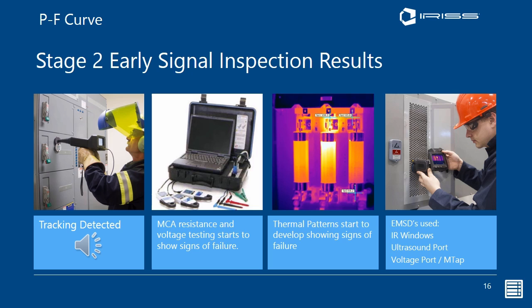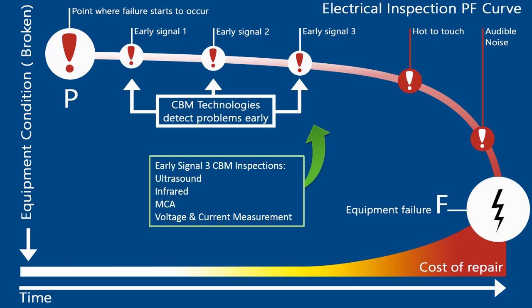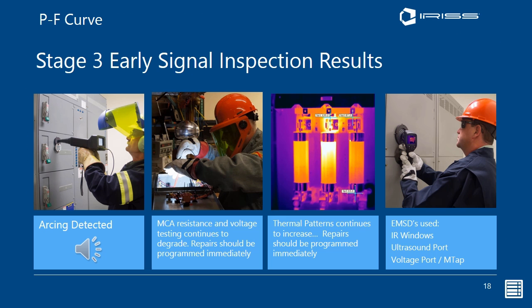At stage 3, we will now start to see possibilities of detecting arc or arcing using the ultrasound equipment. That sounds like this. This is a very distinctive sound. And also at this stage, the motor current analysis and thermal imaging test results will be coming back with significantly elevated temperatures and readings. So really, this is the final stage where we would start to demand or require an immediate shutdown for remedial works, and obviously the infrared, etc., will be showing us what components within the systems are breaking down, so we can order parts that may be required, etc.